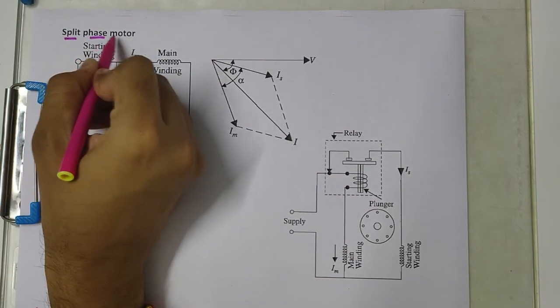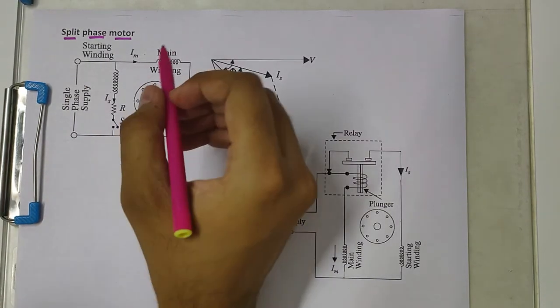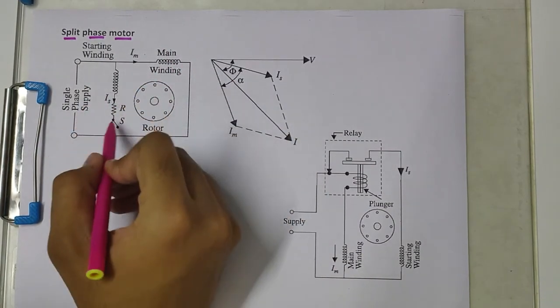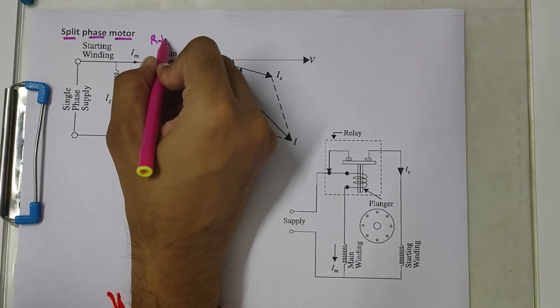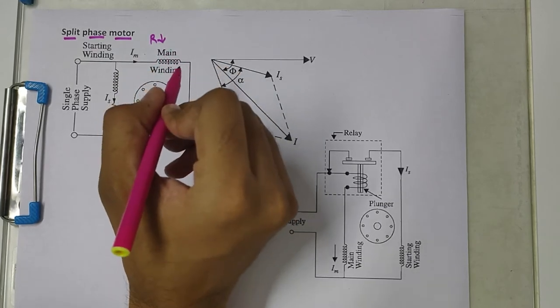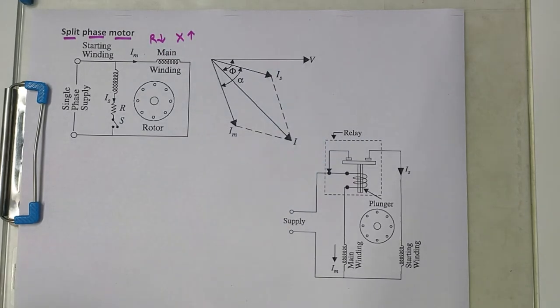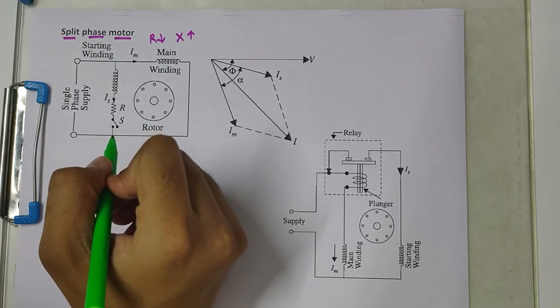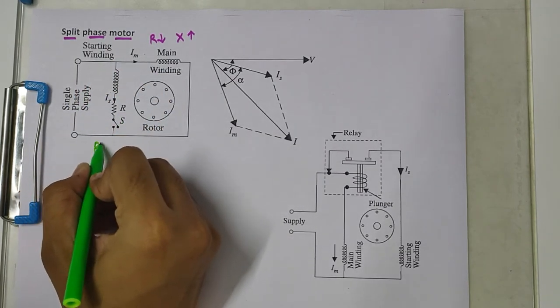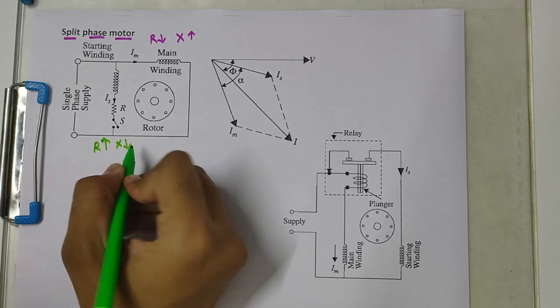Split phase motor is a type of single phase induction motor which has a main winding and a starting winding. The main winding has low resistance. The winding used in the main winding is such that it has low resistance and high reactance, whereas the starting winding combined is such that it has high resistance but low reactance.